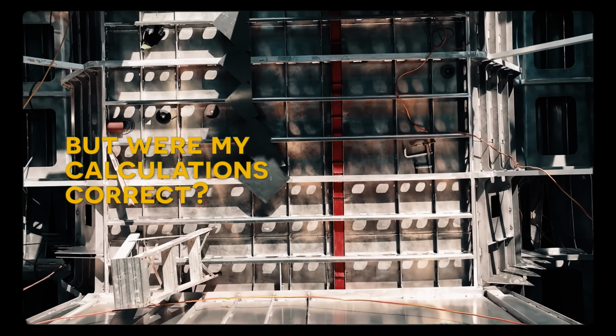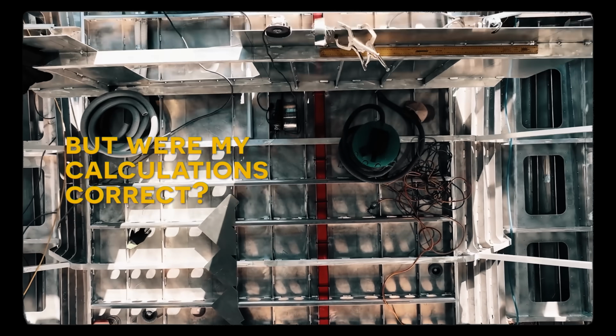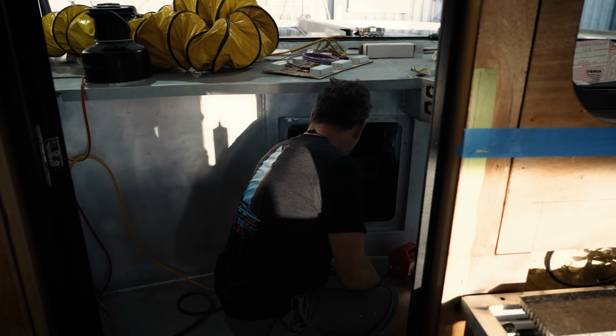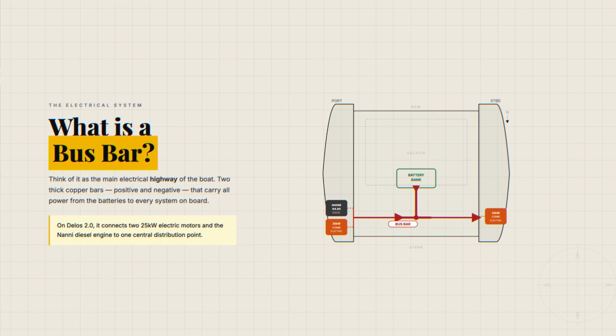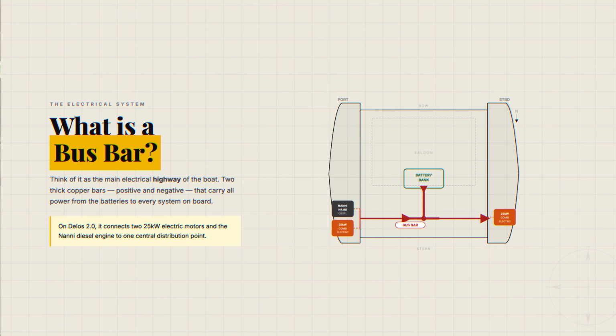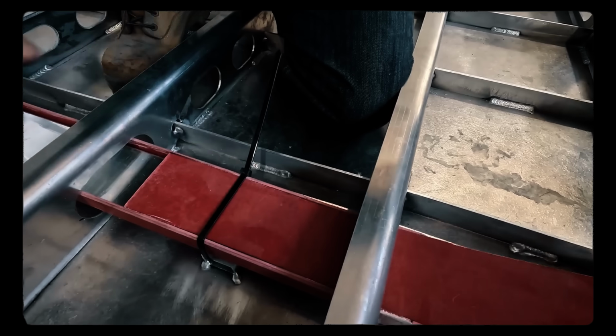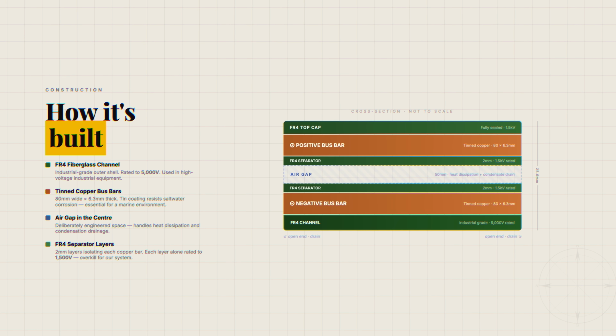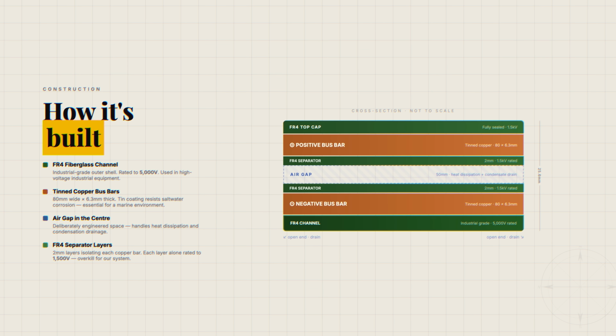But the only question left was whether my calculations were actually correct. First, bear with me on this technical bit, because it matters when we get to the test. Basically, it is a pre-made, prefabricated channel that is meant for high voltage industrial applications. It's 80 millimeters wide on the inside, and the channel is composed of FR4. The channel itself is rated to 5 kV, or 5,000 volts, and the bus bar happens to be 80 millimeters wide, and it's 6.3 millimeters thick. So it's actually fabricated for this particular type of bus bar.